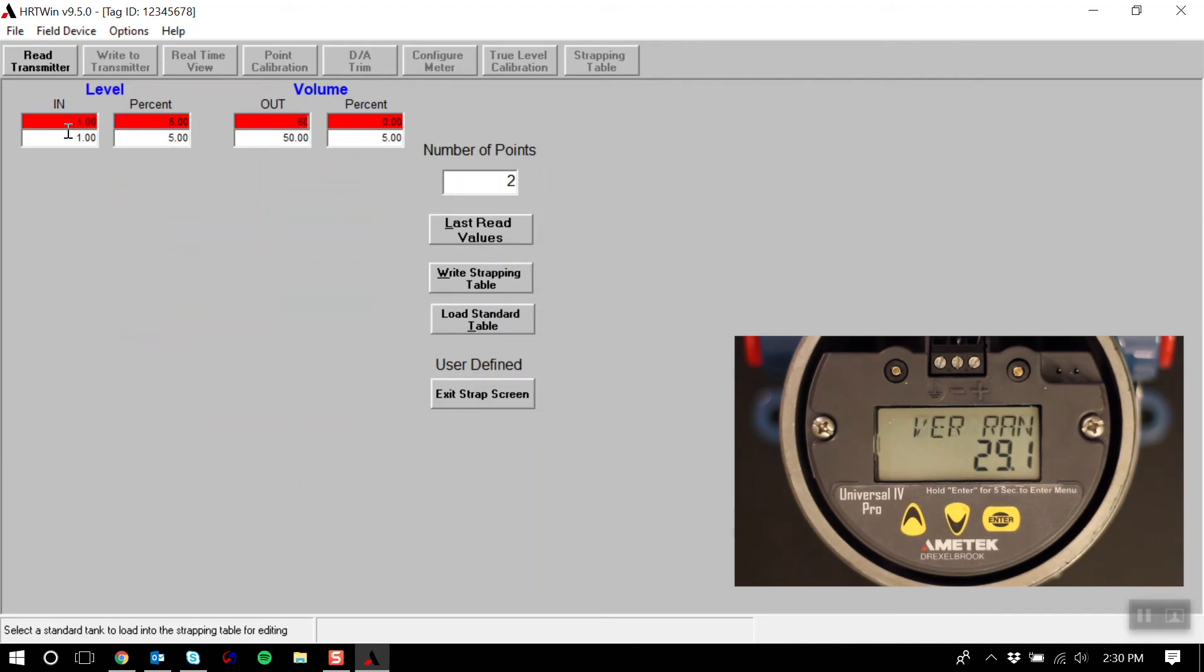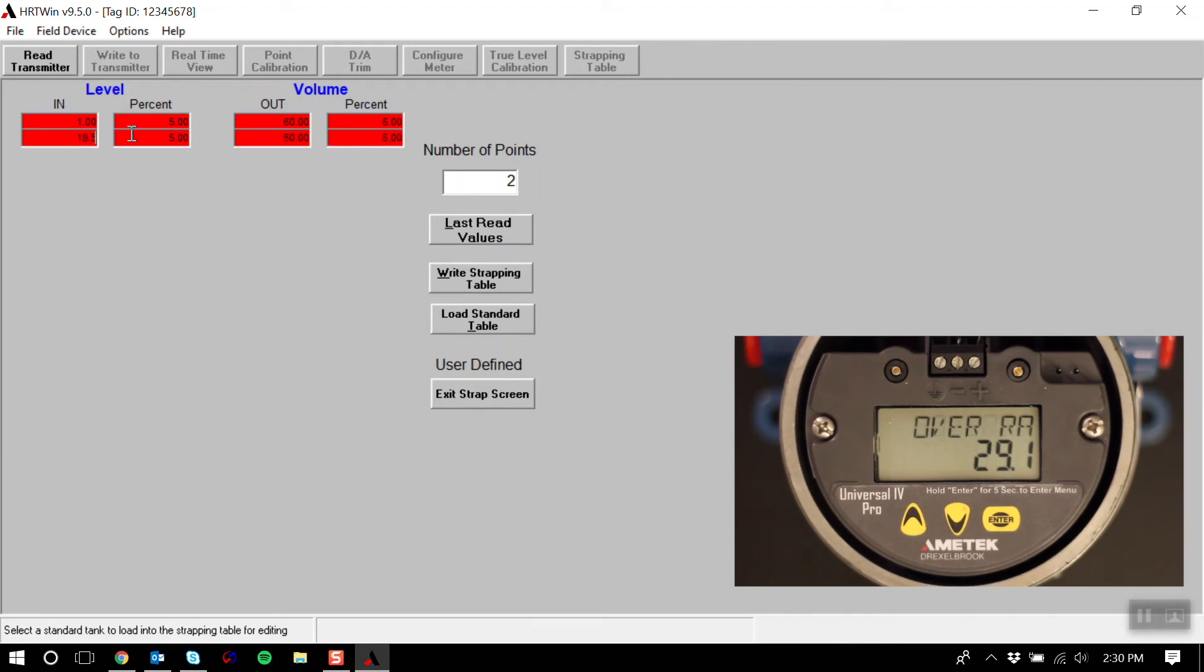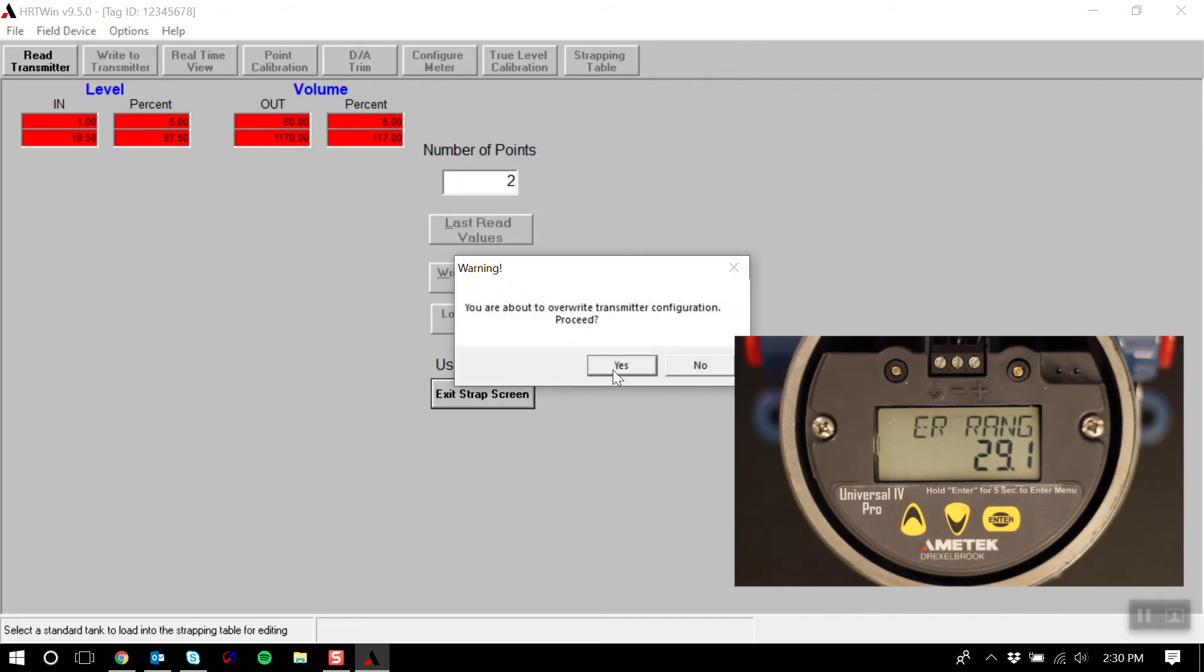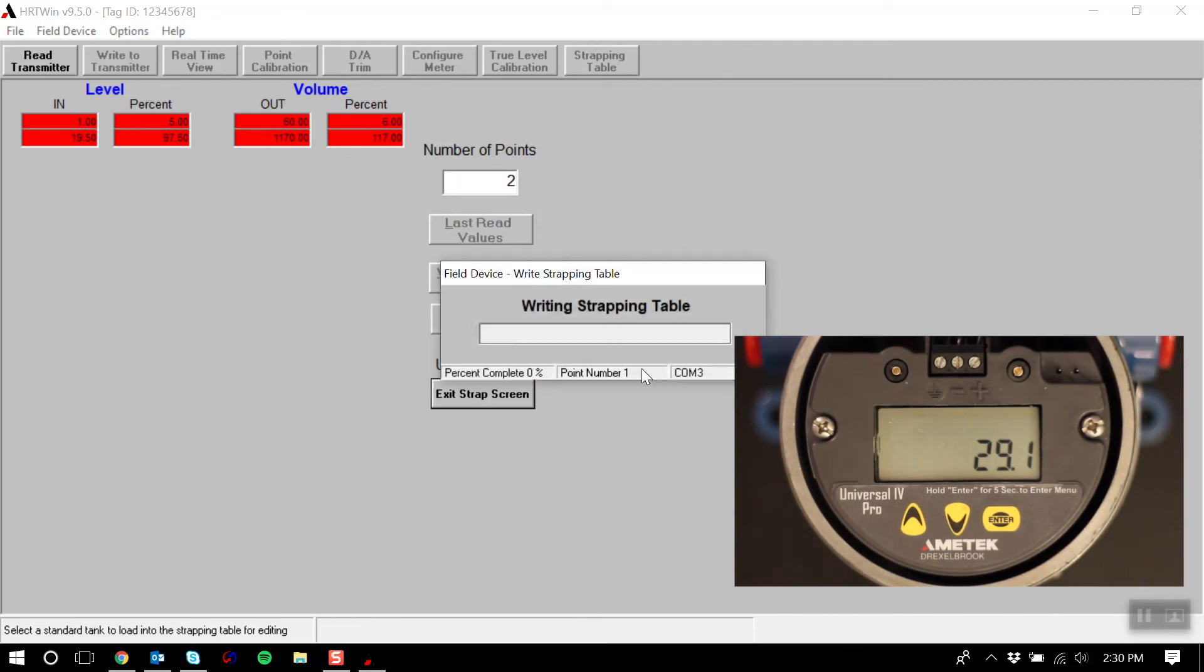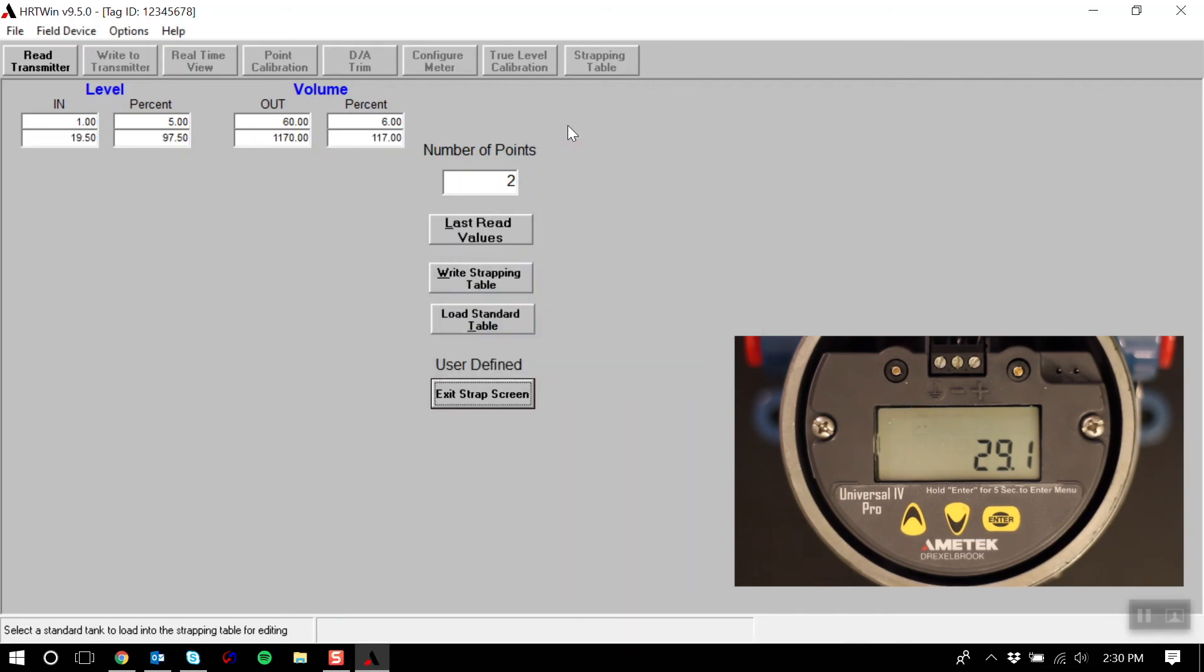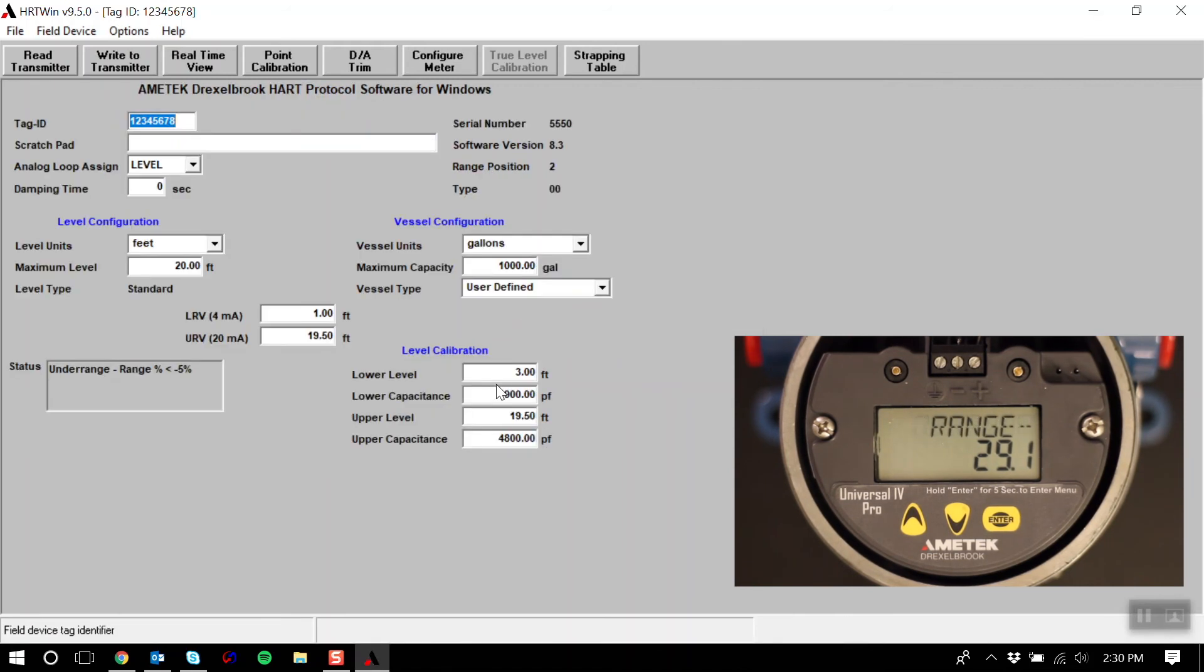And my second point will be 19.5 feet of level, which will equate to 1170 gallons of volume. Once I have the two points that I require, I can write this strapping table to the transmitter. And I'm done. We can exit our strapping table and go back to the main menu, and calibration is complete. It's that simple.